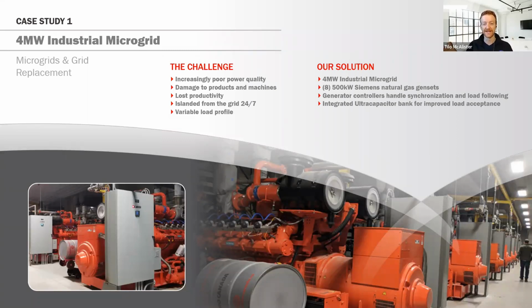But in this case, someone actually cut the cord to the utility system. It was a very challenging project for us, because he was set on this idea of being his own island of production, not dependent on the electrical grid whatsoever. So we had to design a 4 megawatt power plant, fueled by natural gas, the available fuel source there, that could follow his load in an islanded condition.